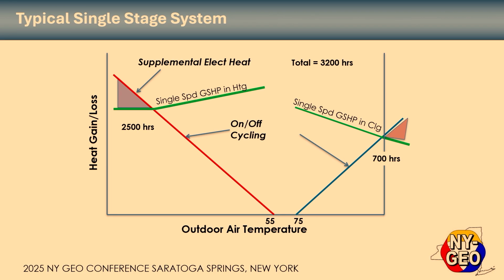But you can see that it hits the load line, and then at the load line, it will probably maintain a temperature. GEO does at least. Air source would keep dropping off. And then, of course, you need to make up this heat here, usually with a supplemental and auxiliary heater. And so that would be called the balance point of the system, and that's really how the heating side is done.